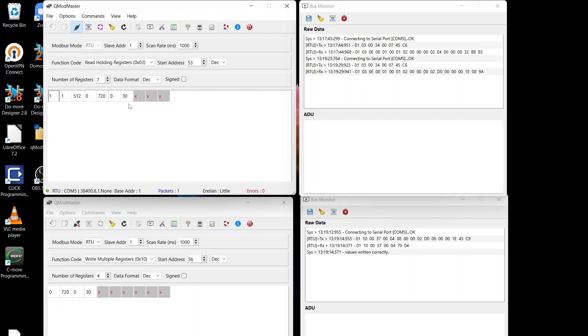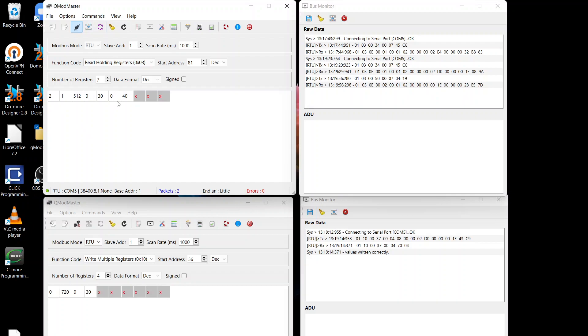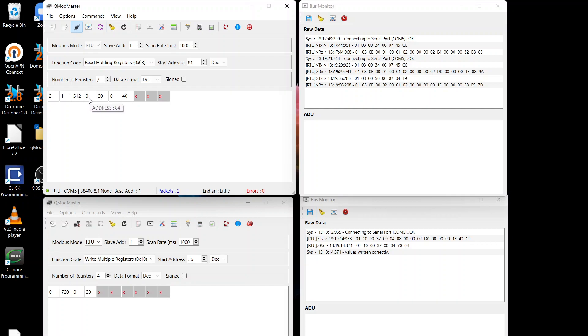Now when we go to the milliamp registers, that's going to be from 81. We'll read the seven registers. So these are the current set values. Two means that it's proportional. One is we're looking at channel 1, which is the pH. The bit mask 512 is showing the errors. And then we've got currently it's set at 0.3 with an offset of 0.4. So that would mean that the pH would be going from 0.3 to 0.7.